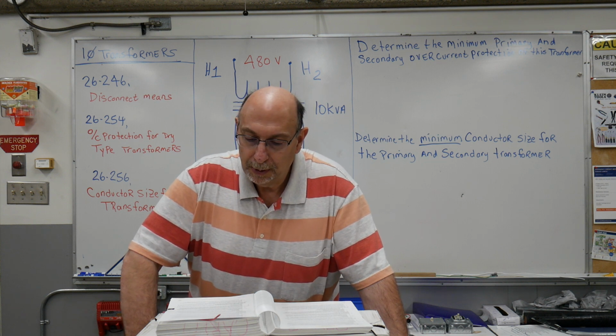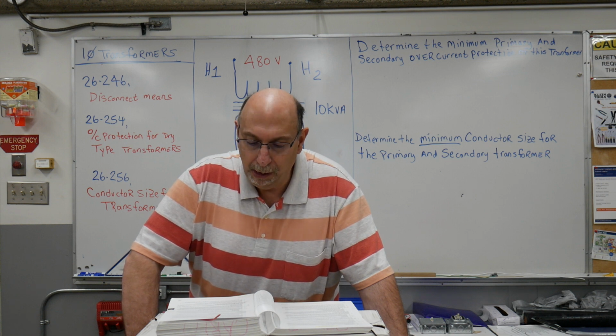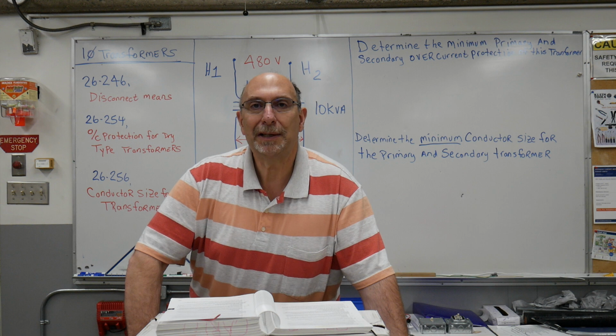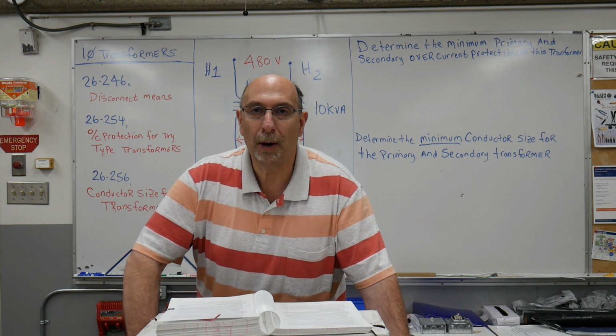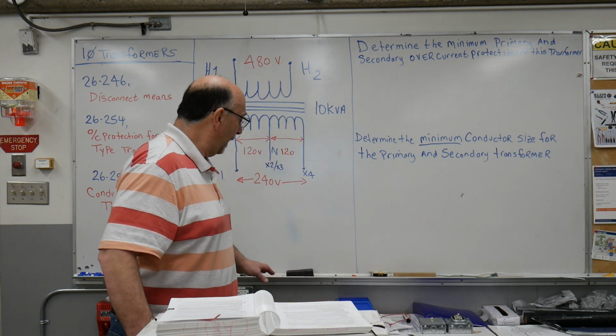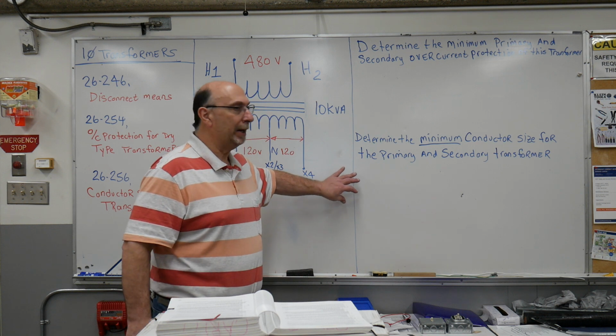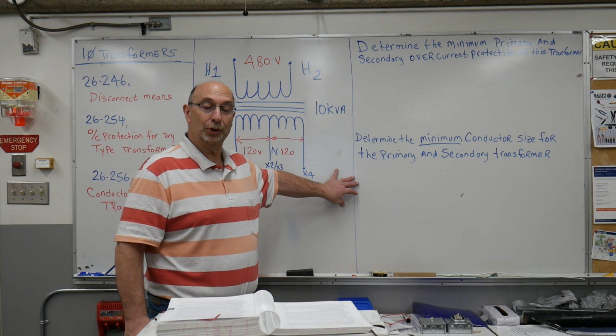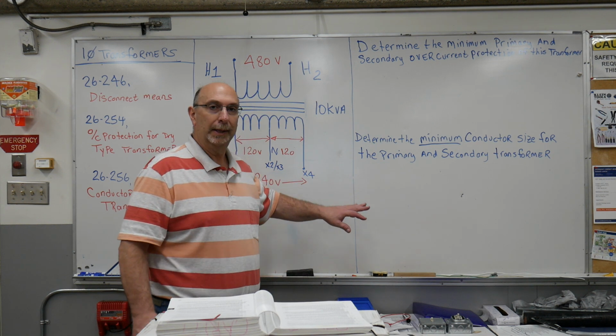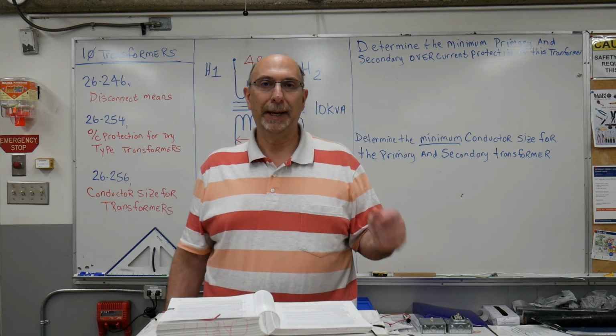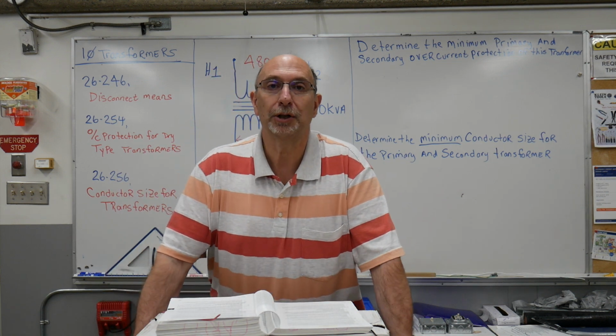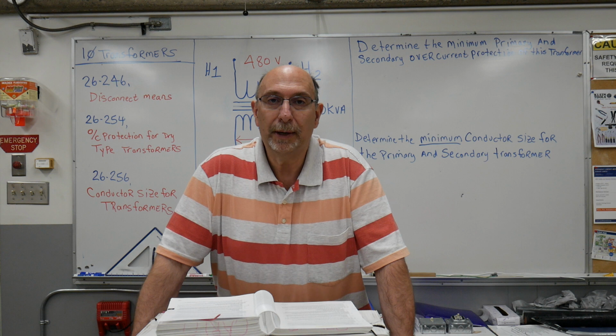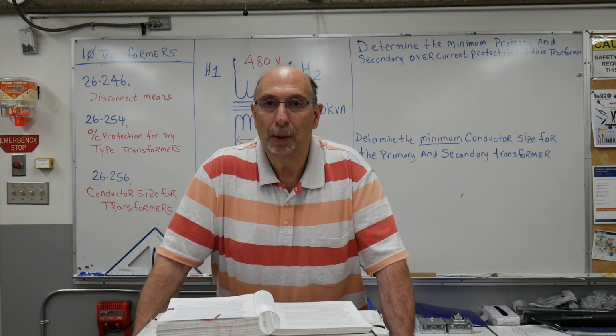Sub-rule 2 says where the adjacent surface is a combustible material, the separation has to be 300 millimeters or 12 inches. So for example, if we had a transformer located next to a drywalled wall, that transformer has to be at least 300 millimeters or 12 inches, 1 foot away from the wall. The paper will burn.